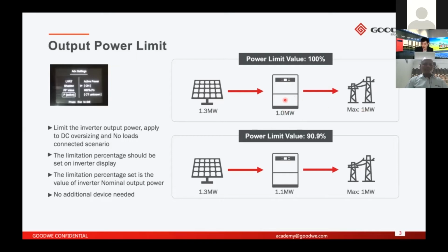But for our product, we have the AC overload ability. That means if you have more PV modules on the DC side, sometimes the inverter output will be more than 1 megawatt because of the AC overload ability. So in this case, if you just want to output 1 megawatt to the grid, you need to limit the inverter output. If the inverter capacity is 1 megawatt, you can set the power limit value to 100% in the inverter display. In the display, you can set the power limit value. So the maximum output power to the grid will be 1 megawatt.